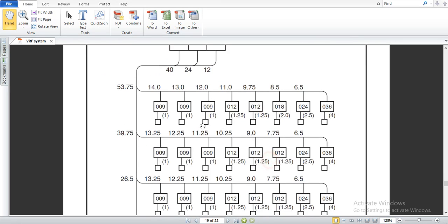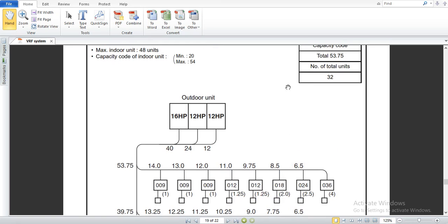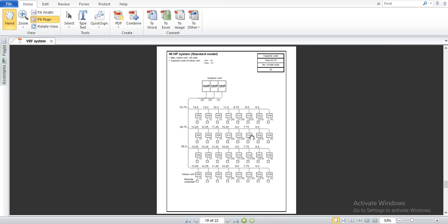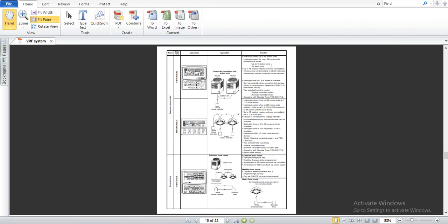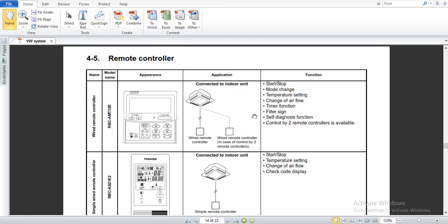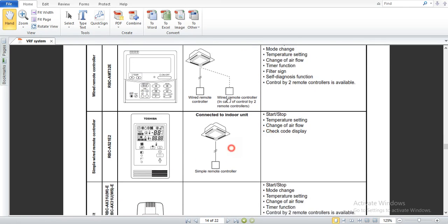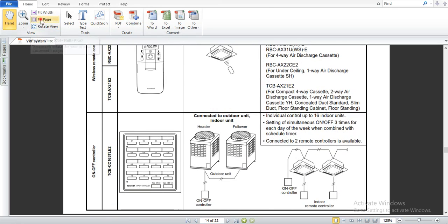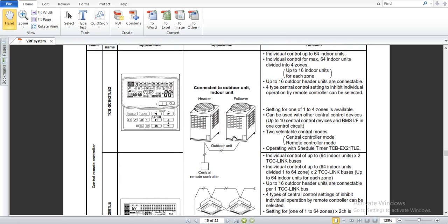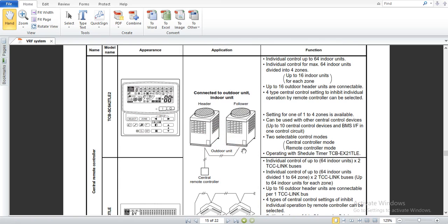This is how you can select your machines based on your number of indoor units and the capacity code of the indoor units — selecting indoor and outdoor units based on your heat load calculations. One more thing to explain is the remote control for the VRF system. Different types of remote controllers are available: it could be wired, it could be wireless, or it could be a central remote controller. Depending on the type of application and number of zones, you can select the appropriate remote controller for your system.